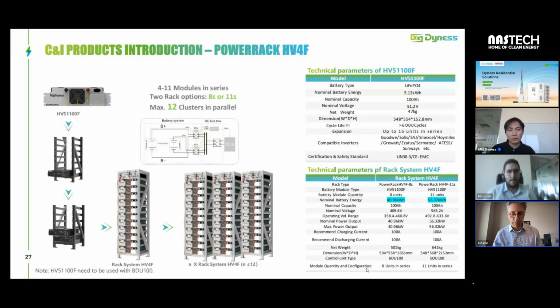When we say high voltage, these inverters are three-phase, and the output for the load is around 400 volts. But on the battery side, we're talking about 150 volts up to 900, in some cases even 1000 volts. So this is not like a typical low voltage battery - you need a high voltage battery, which, as Oscar explained, is a very good product with internal cooling, this HV4F.